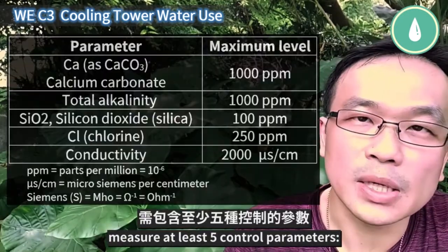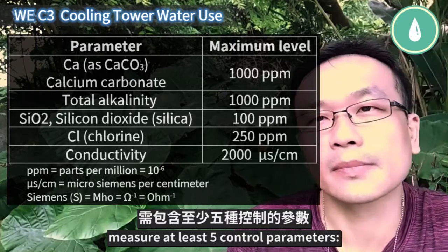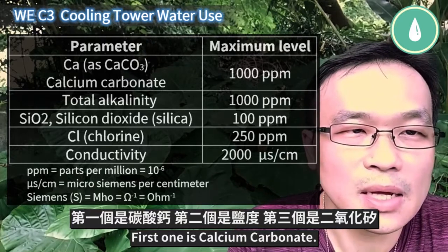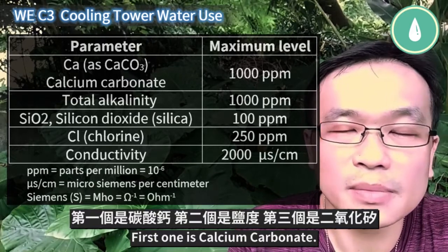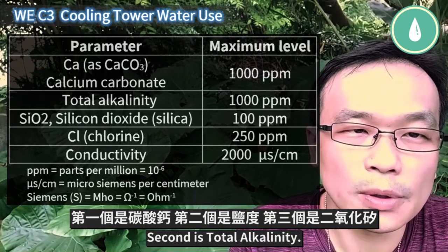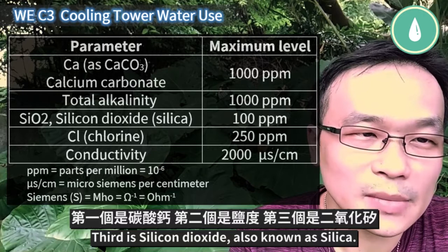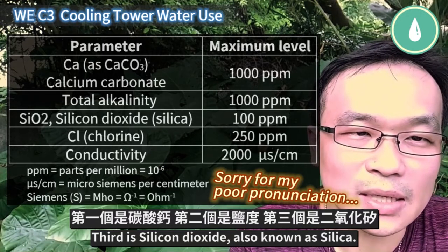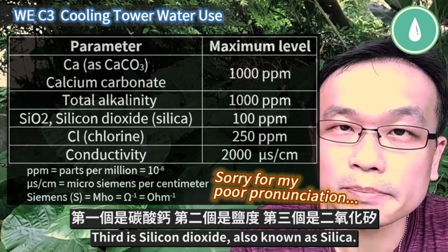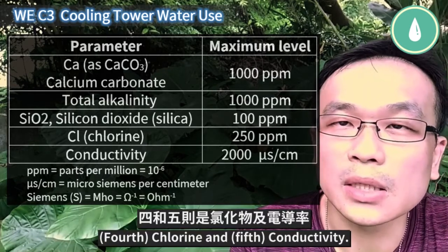You must conduct a one-time potable water analysis for cooling towers and evaporative condensers. Measure at least five control parameters: first, calcium carbonate; second, total alkalinity; third, silicon dioxide, also known as silica; fourth, chlorine; and fifth, conductivity.